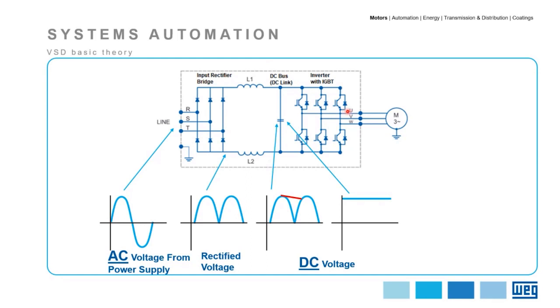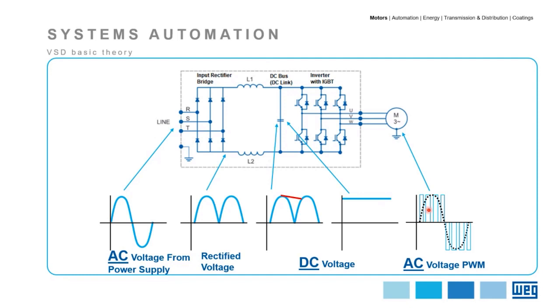This is where the magic happens. The inverter, which is composed of six IGBTs (Insulated Gate Bipolar Transistors), converts the DC voltage to an AC voltage by using the PWM (Pulse Width Modulation) technique. The IGBTs switch in such a way that these voltage pulses can be controlled, and as a consequence, a variable voltage and frequency at the output can be generated. This is a basic understanding of the VFD.